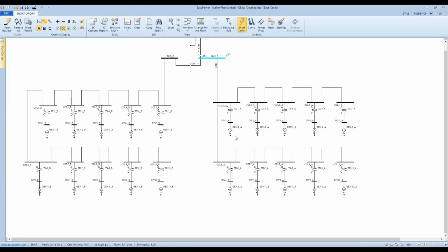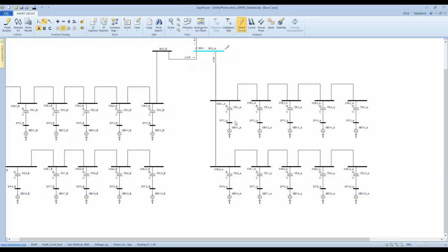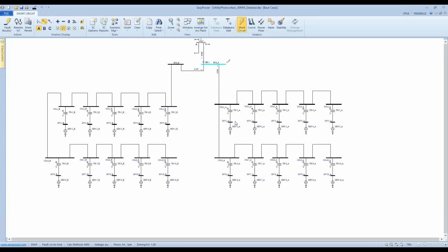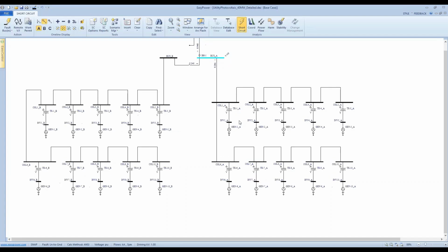Because you cannot use a lumped equivalent generator to represent all of them, right? Their MVA rating is different. Their subtransient impedance and transient impedance are different, maybe. And also their stability models are different. So you cannot use one unique generator to represent all of them. Now, this introduces the concept of grouping, which means that we need to model different types of inverter using different types of lumped equivalent.